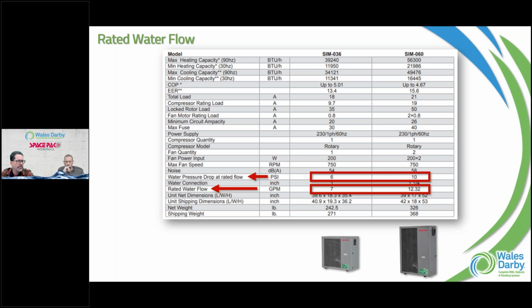So we're asking about temperature rise, and thinking this is a closed system, the return water from your system if we're max at 120. It depends on the circulator too, what size and how we move the water through. But typically, I want to say it was a 10 to 20 degree delta that we're designing off of. It's a good question. I know we had the conversations, just not top of my head right now what that number was.